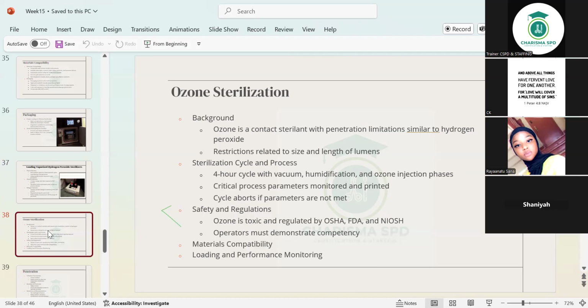Okay. So restrictions related to size and length of lumens, this is going to be by the IFU. It has some restrictions to certain things that can go in, like channeled instruments, okay? Instruments with holes, with canals in them. The cycle and process, it has a 4-hour cycle with vacuum, humidification, and ozone injection phases. 4-hour cycle. Maybe that is why I don't like it.